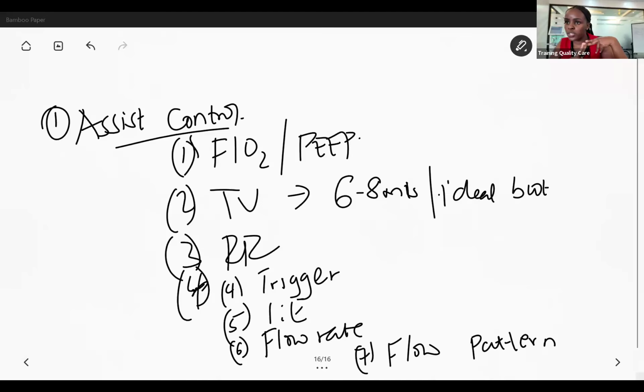That is, you should be able to set the respiratory rate, if you're giving full support to the patient. The other thing is pressure or volume cycle, and either pressure support for that patient, which the mode allows. So you have to ensure that, depending on your patient, if your ventilator does not allow you to set the other settings, the safe one is to use the mode known as synchronized intermittent mandatory ventilation, where the patient can initiate their own breath.